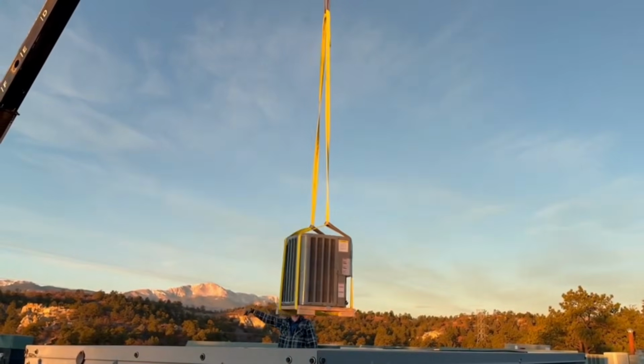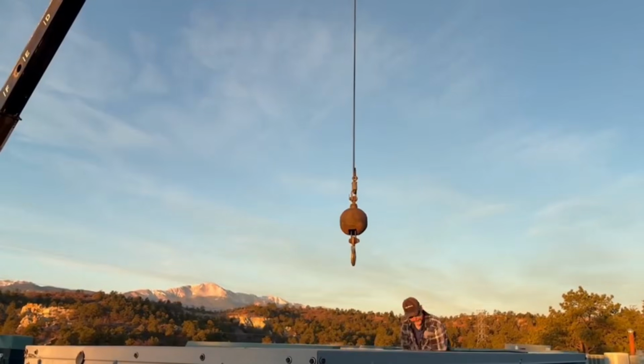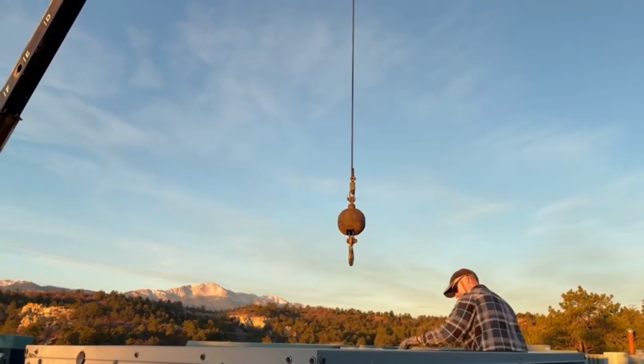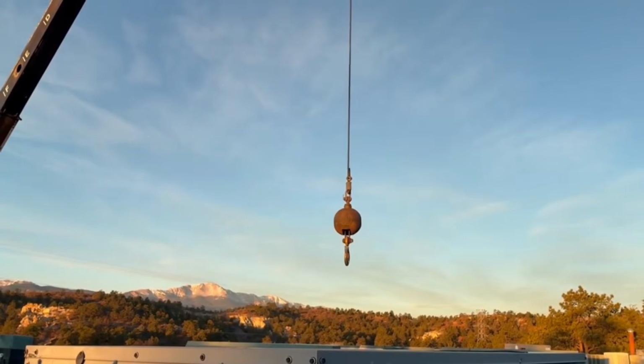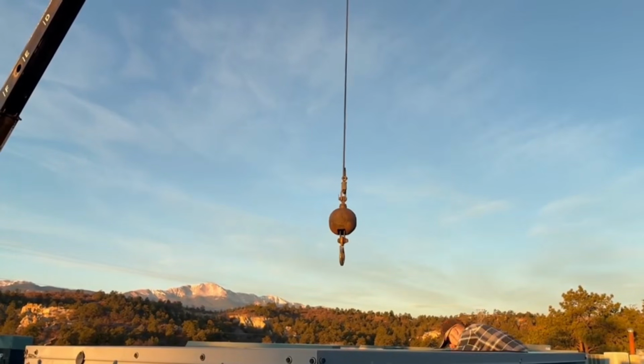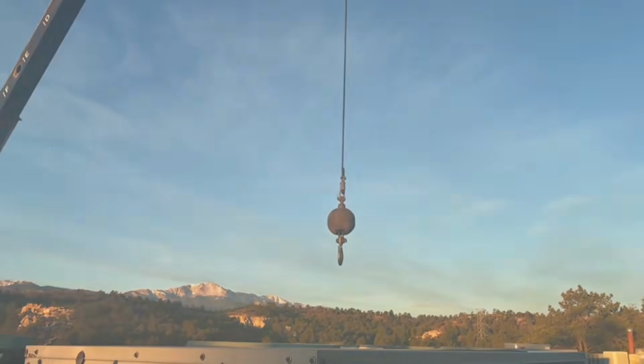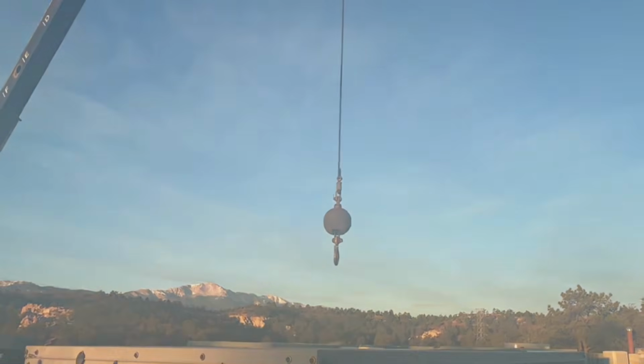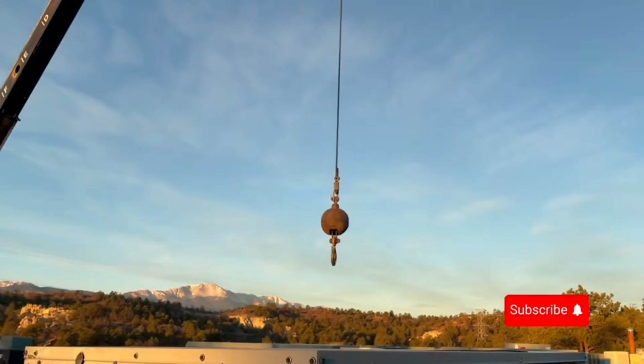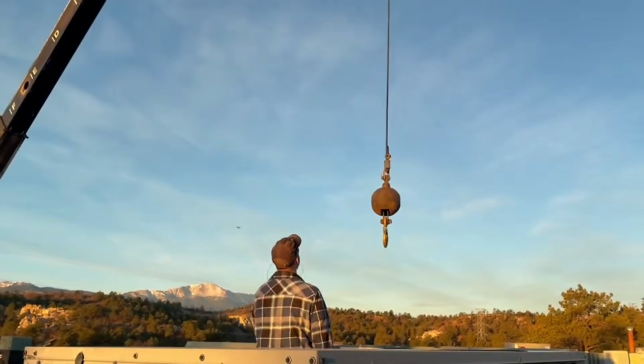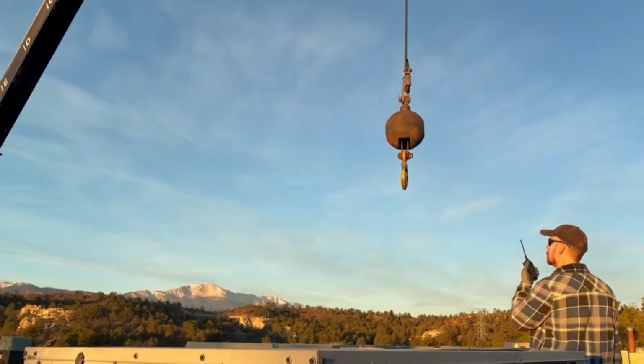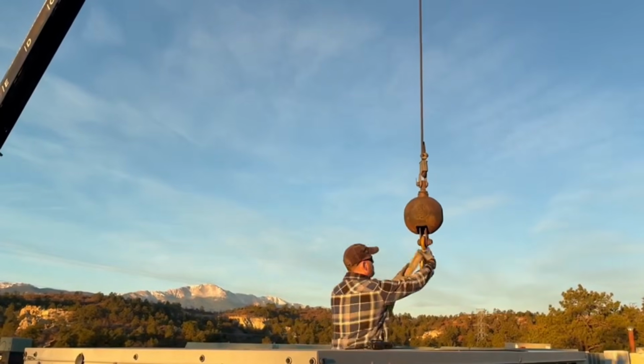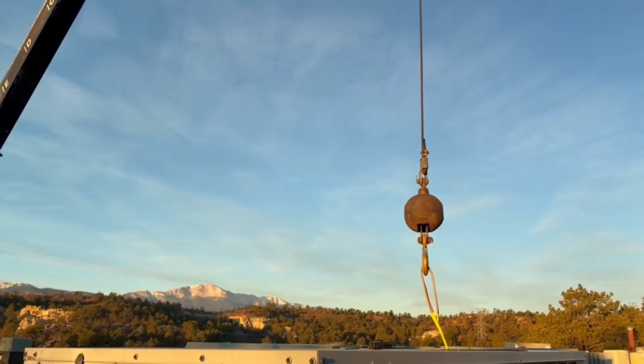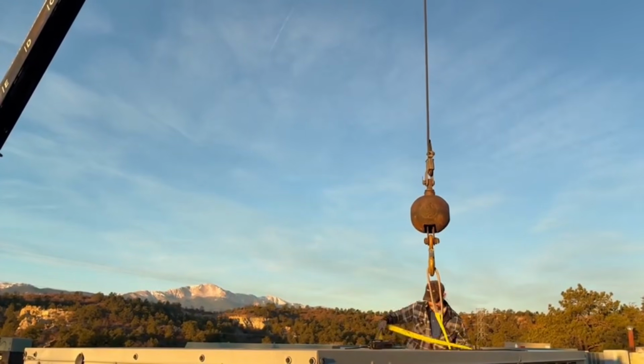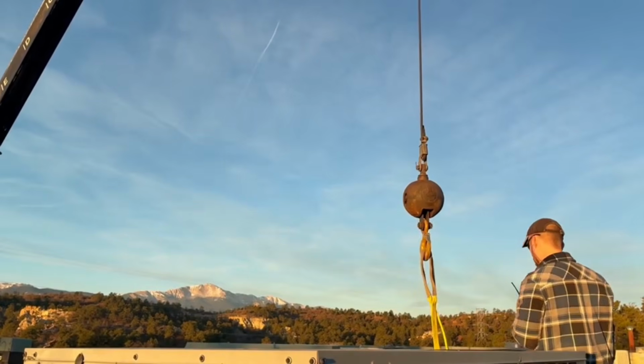A crane arrived. We're going to lift the new unit onto the roof. Then we'll hook up the old unit and lift the old unit off the roof. Trying to get the old unit balanced and find a good way to rig it up so it was safe to lift. Just communicating with the crane operator. So we'll hook up the straps. And you want to make sure you have everything ready to lift off the roof before the crane arrives, because cranes can be expensive to rent.